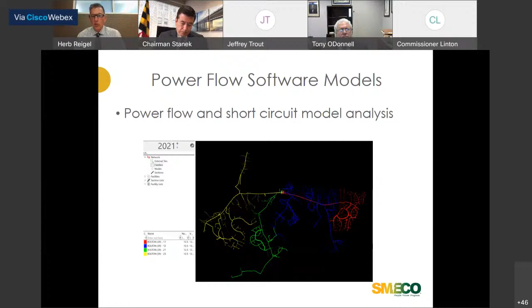A couple of slides here show what the output of these reports and system analysis look like. One set of analysis for this substation provides power flow results similar to what you see on the screen. It shows percent loadings of not only individual feeder circuits but also specific local line sections associated with each feeder circuit, the demand on those circuits, any current or voltage imbalance, the connected customer load on each circuit, and any areas experiencing higher than normal line losses that might be a target for a system upgrade.